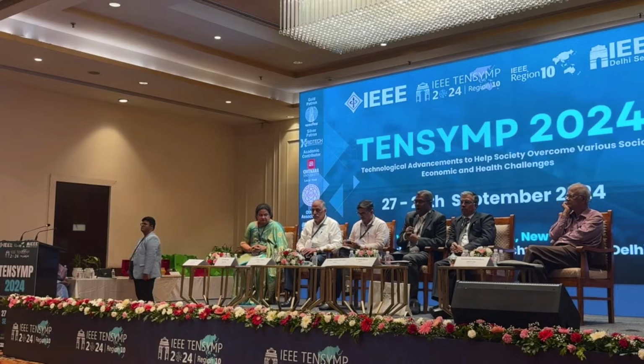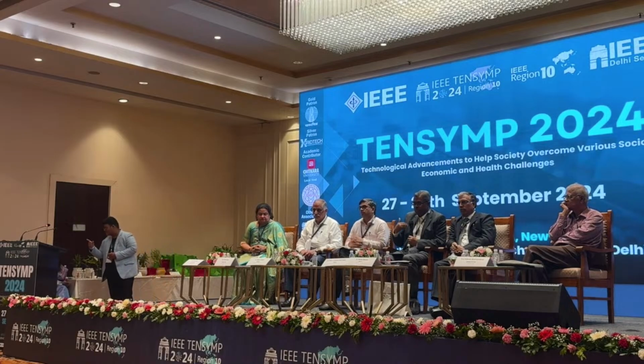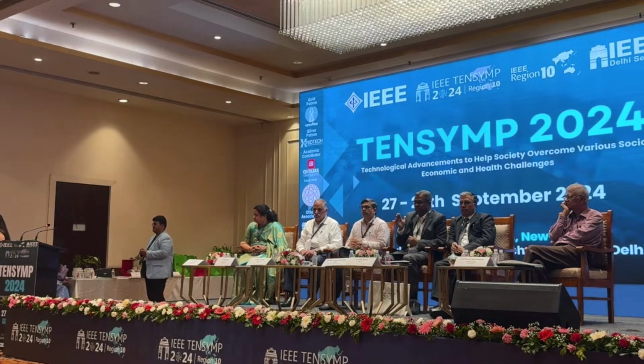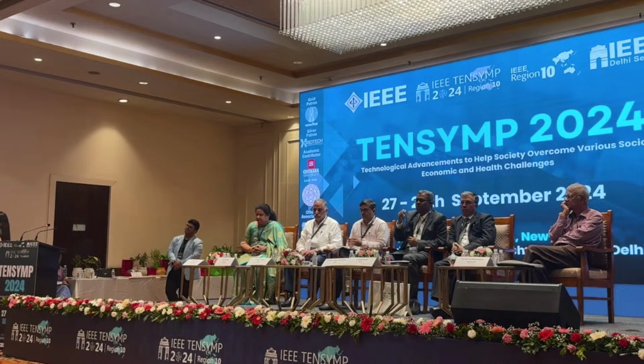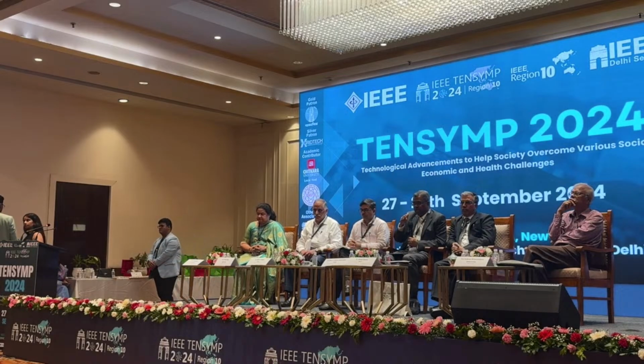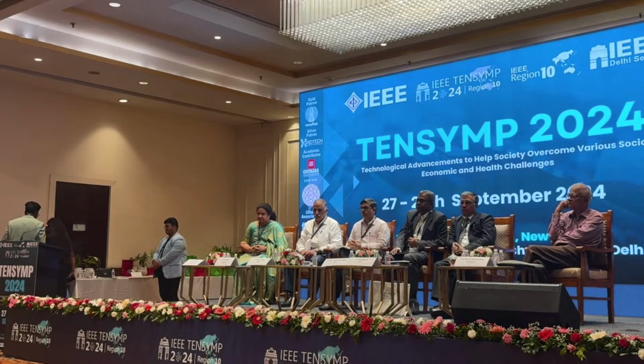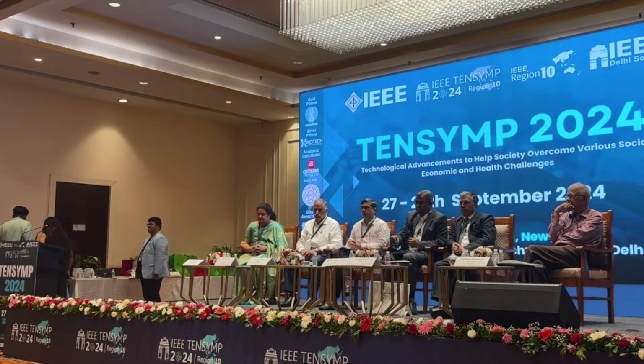Third, come to hydro. We have around 47-48 gigawatt installed capacity. In northern India hydro is largely snow-fed, run of the river, with few reservoirs. In the south it's monsoon dependent and reservoir based. Hydro is highly seasonal and very precious, so it's conserved to the extent possible; otherwise it runs as run-of-the-river. During high hydro season we have achieved a maximum of around 41-42 gigawatt out of 47 gigawatt capacity, in July, August, and part of September. But in winter nights hydro goes down to 5 gigawatt, and it's conserved to meet peak demand, which in winters is achievable at around 19 to 20 gigawatt.